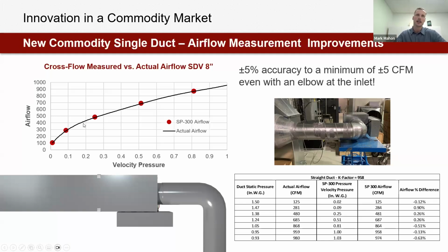So what we can see here is the actual airflow measured in our laboratory, and then the cross-flow sensor airflow at these 5 points throughout the range of an 8-inch single duct box here. And what we found was even with an elbow directly on the inlet, we were actually plus or minus less than 1%. With an elbow directly on the inlet. So we did a ton of testing to quantify this, and we actually have updated our documentation.